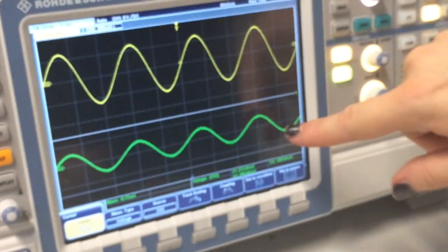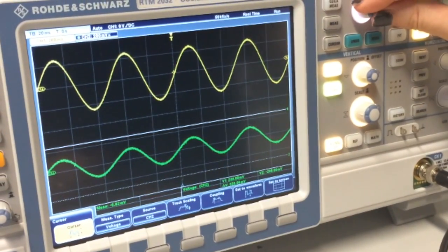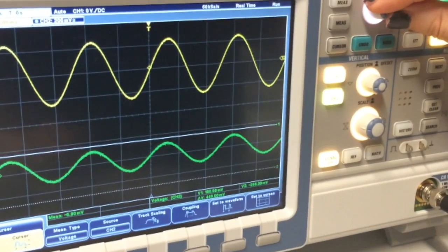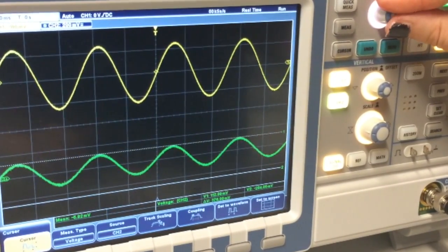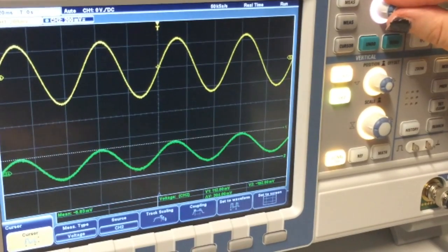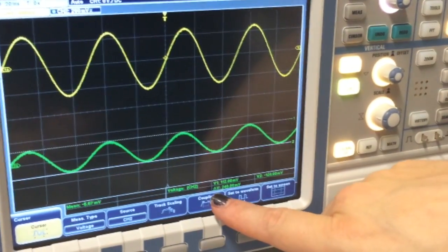So now you've got that here, what we're going to do is measure. So I shall move this down, like so. Press the button in, move this one up, like so. And you can see that the change in voltage there is currently now less than it was before. It's 240 millivolts. And just do that for every frequency there is.